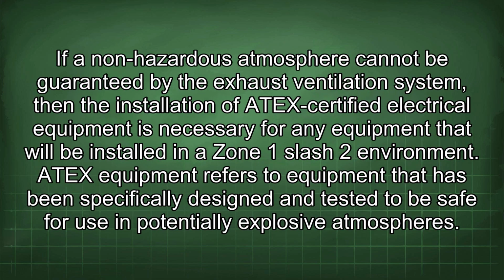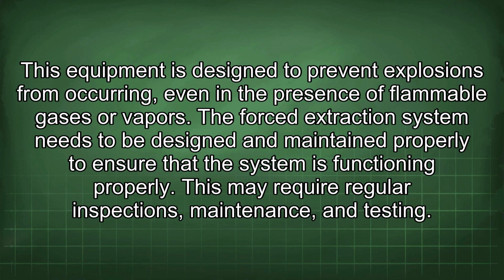If a non-hazardous atmosphere cannot be guaranteed by the exhaust ventilation system, then the installation of ATEX-certified electrical equipment is necessary for any equipment that will be installed in a Zone 1/2 environment. ATEX equipment refers to equipment that has been specifically designed and tested to be safe for use in potentially explosive atmospheres. This equipment is designed to prevent explosions from occurring, even in the presence of flammable gases or vapors.